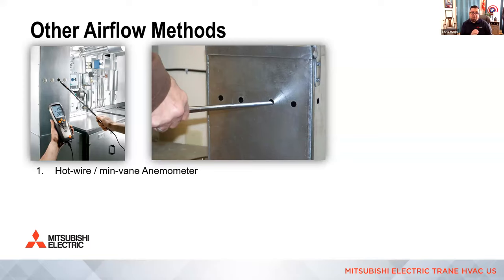So there are approved airflow methods of measuring. I personally am not a fan, even though I own a hot wire and a min-vane anemometer. These measurements are not very repeatable. Every time I take this measurement, because my hand's slightly different or the angle's just off a little bit, the measurement's always different. It's usually within 10% of what I measured last time. But because it's not as repeatable, I don't recommend it very often.